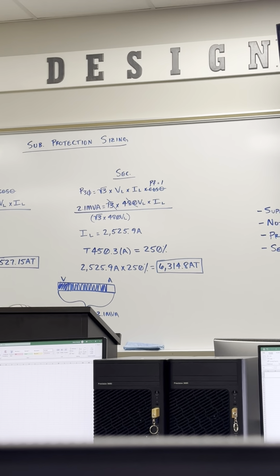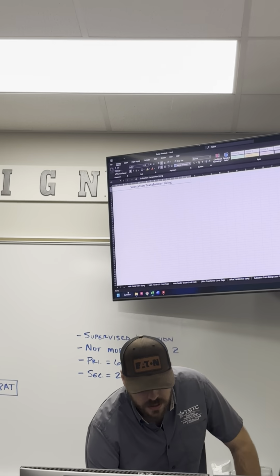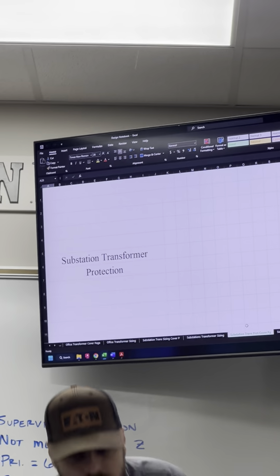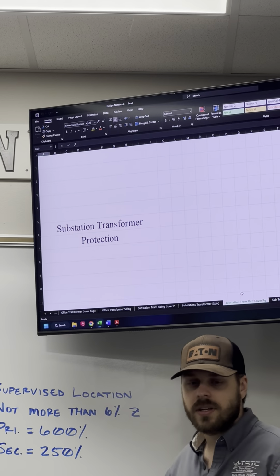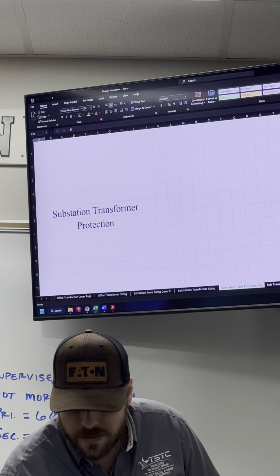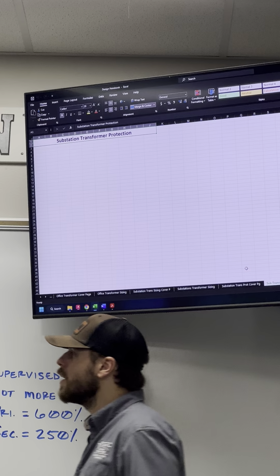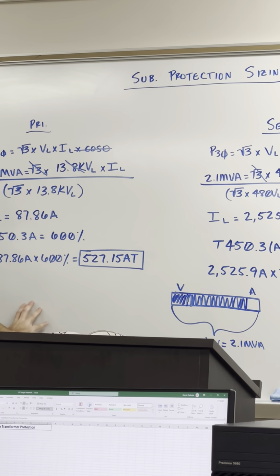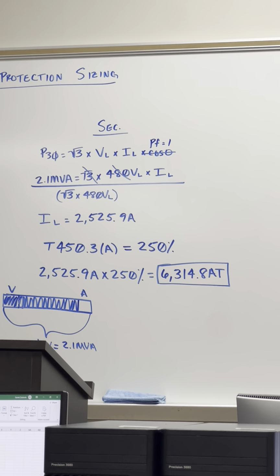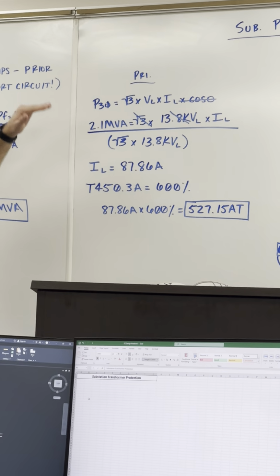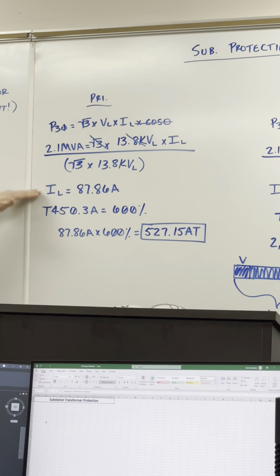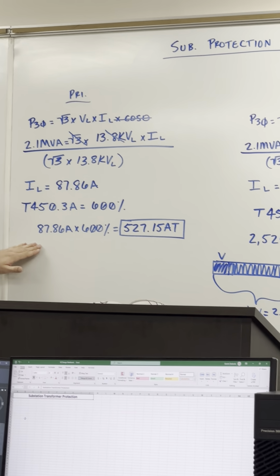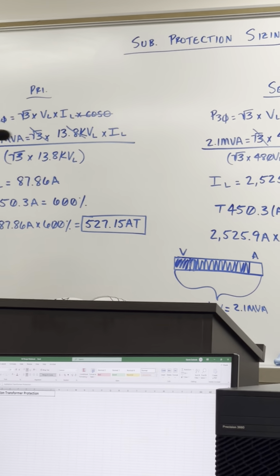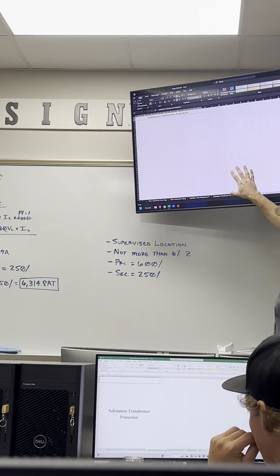So coming back over here to your notebook, here was the transformer sizing page. The page directly after that is our substation protection cover page. And then the tab after that, same thing, it's a blank page to show your work. So you need to show what we just did right here. You need to show one for your primary side, one for your secondary side. You'll show the same process. Show your three-phase equation, plug in your values, solve for I line, show your table percentage, show the math of doing that and what you calculate and what your breaker calibration settings are. But all of that will need to go on this page here.